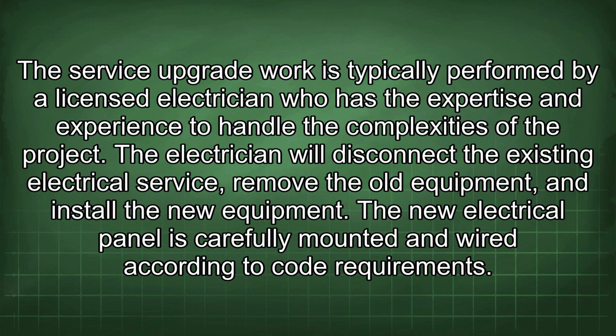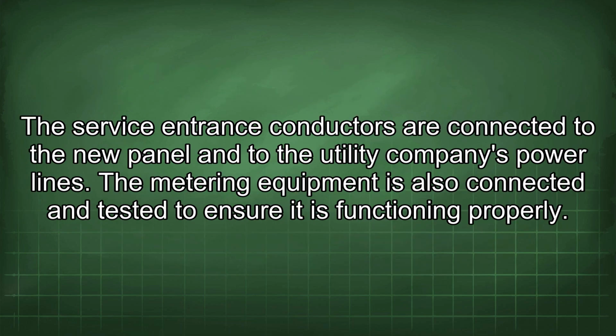The service upgrade work is typically performed by a licensed electrician who has the expertise and experience to handle the complexities of the project. The electrician will disconnect the existing electrical service, remove the old equipment, and install the new equipment. The new electrical panel is carefully mounted and wired according to code requirements. The service entrance conductors are connected to the new panel and to the utility company's power lines. The metering equipment is also connected and tested to ensure it is functioning properly.